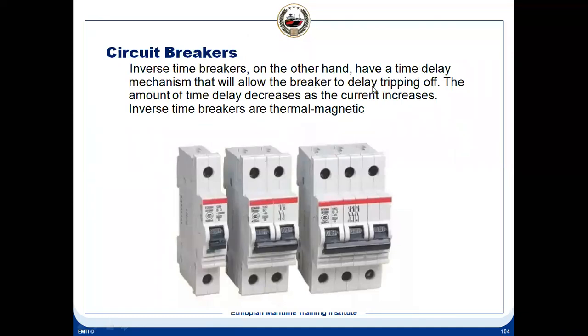This is the inverse time breaker. Inverse time breakers, on the other hand, have a time delay that will allow the breaker to delay the tripping. The amount of the time delay decreases as the current increases. That is why it is known as inverse time. That means if the current increases, the time delay will decrease. If the current is less, the time delay will become more.